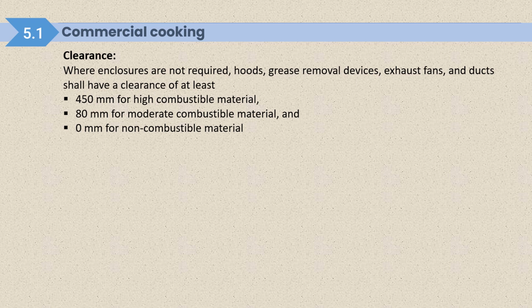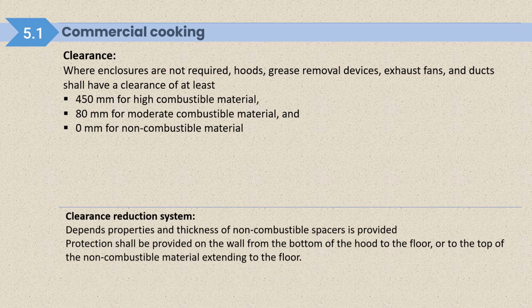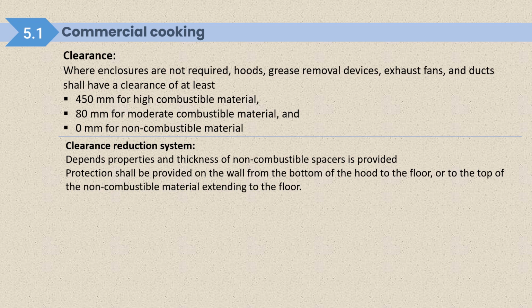If the hood or duct is nearby any combustible materials, then we have to maintain a gap of 450 mm. If moderate combustible material is there, then we need to maintain a gap of 80 mm between the duct and the moderate combustible material, and 0 mm in case non-combustible material is nearby. Clearance reduction system depends on the properties and thickness of the non-combustible spacer provided. Suppose we are not able to maintain the gap mentioned above. In that case, we need to provide a non-combustible spacer between the duct and the combustible material.